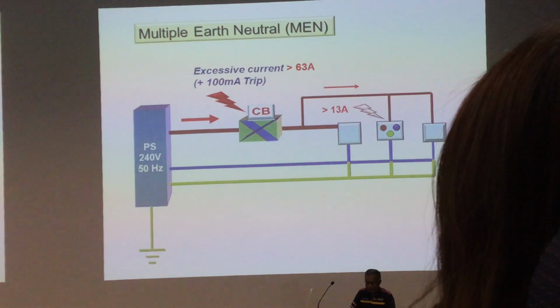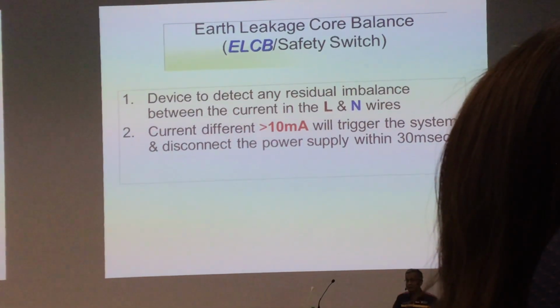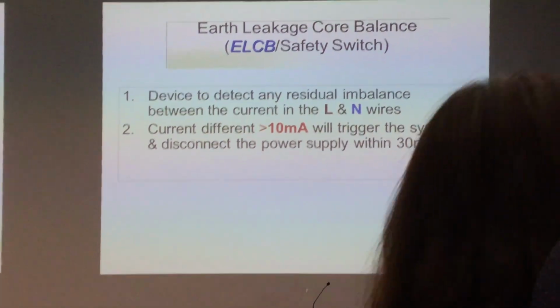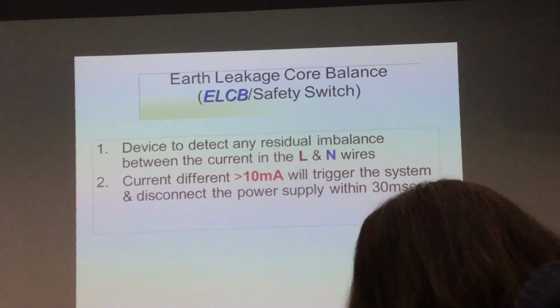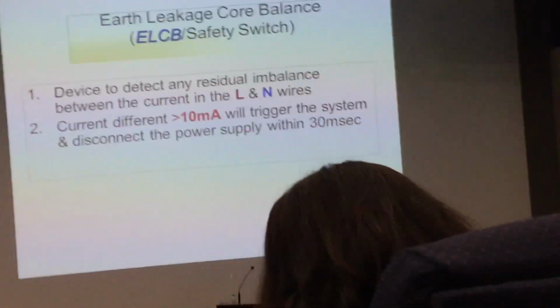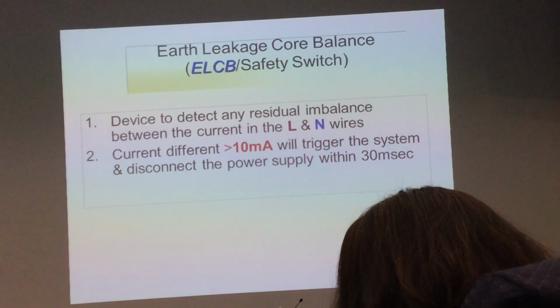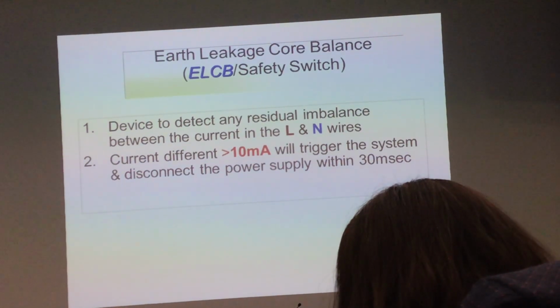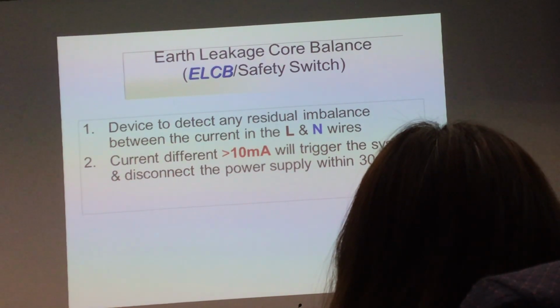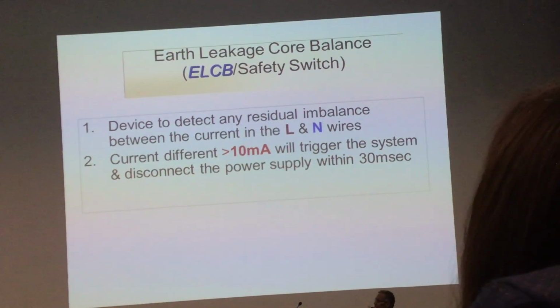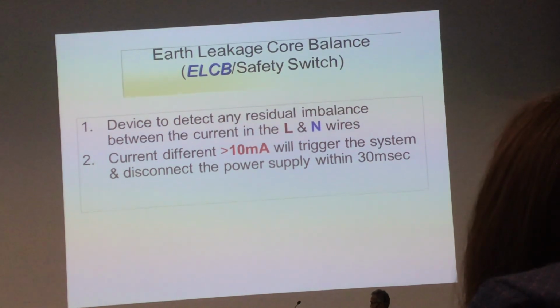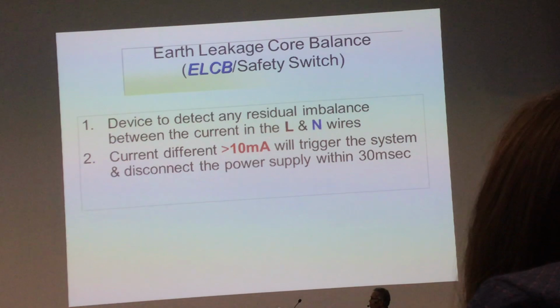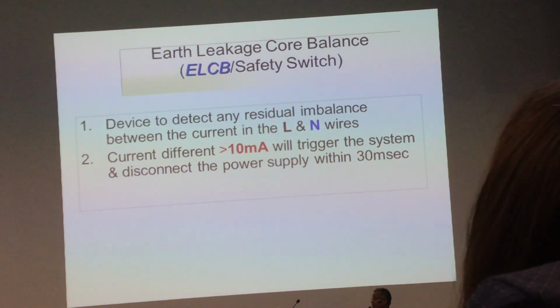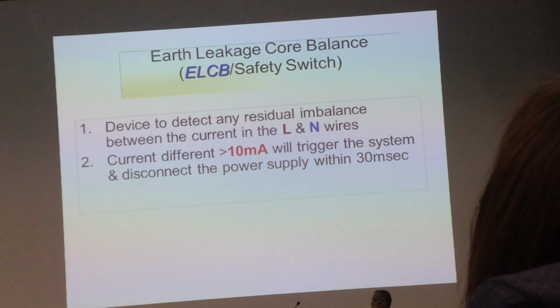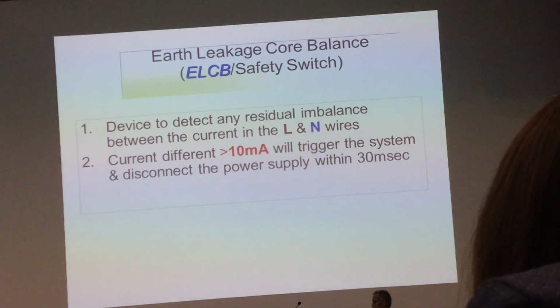Okay, now the circuit breaker, CB or fuse. Number 2, the ELCB. The second method of preventing electrical hazard is by using ELCB. Earth leakage core balance is normally used in non-cardiac OT. Now modern OTs all use class 1. All OTs regardless of cardiac or non-cardiac, all class 1. But older OTs use ELCB, or at home, especially for certain devices like hot shower, iron, electrical cooker, or those appliances, they use ELCB to protect the user.